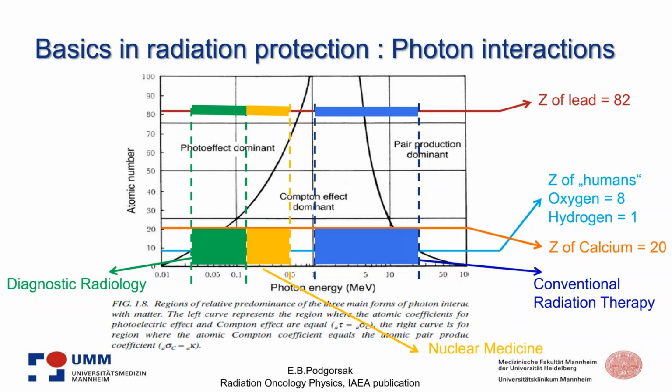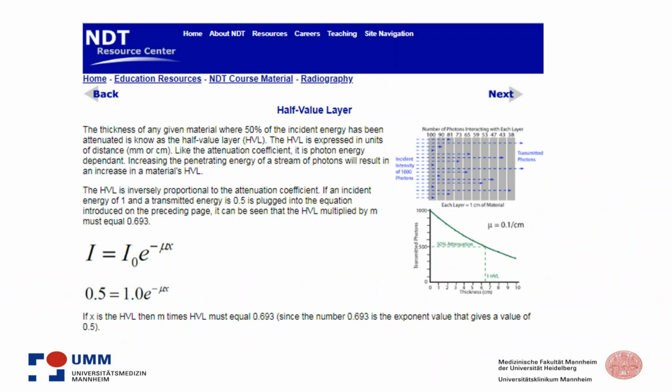Also in the background, at the bottom line, we have again the patient area, and if we go up into the shielding area where we need high Z to protect from the radiation, you see we also have photo and Compton effect, and the higher the energy and the higher the Z, we have a pair production dominant part. For this pair production dominant area we have a kind of activation, and this is what I will point out later on.